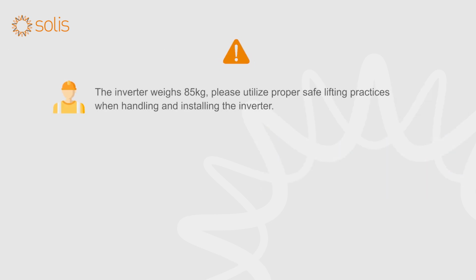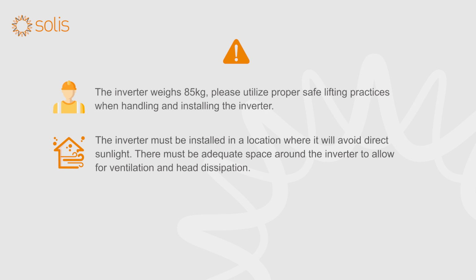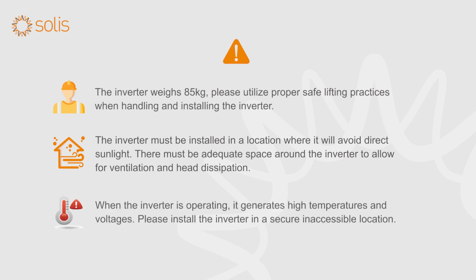The inverter weighs 85 kilograms. Please utilize proper safe lifting practices when handling and installing the inverter. The inverter must be installed in a location where it will avoid direct sunlight. There must be adequate space around the inverter to allow for ventilation and heat dissipation. When the inverter is operating, it generates high temperatures and voltages. Please install the inverter in a secure, inaccessible location.